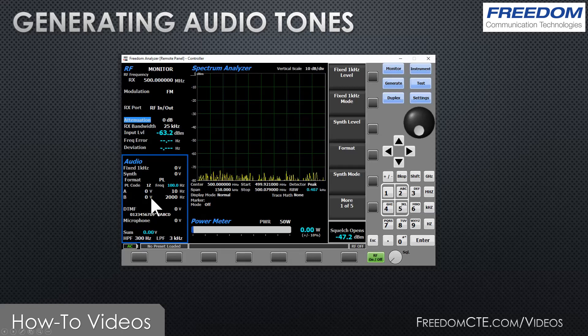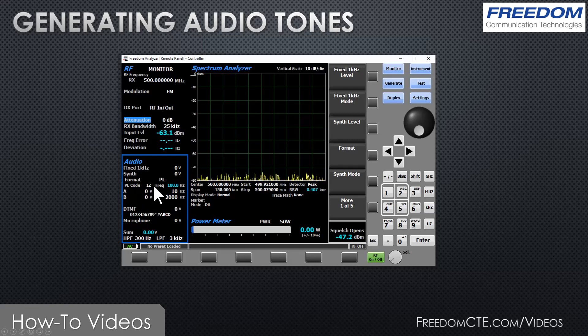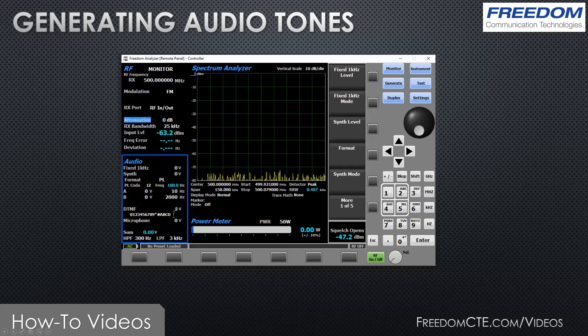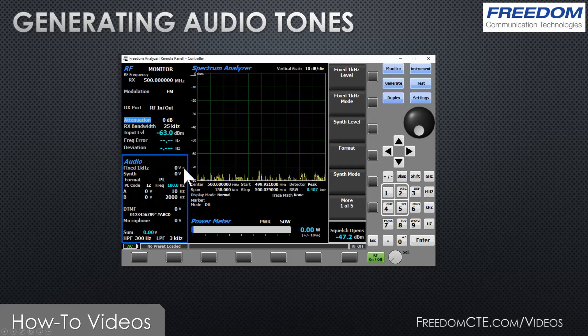The most important thing you should realize upfront is that there are basically two modes of operation. Right now I'm in monitor mode, as you can see up here. By pressing the blue monitor button I'm in monitor mode. In this mode I am NOT generating a carrier, therefore I'm not modulating a carrier with the audio. The audio zone can be thought of as an audio function generator. The audio that I configure here will be available at the mod out port on the front of the instrument, so all of my settings use the units of volts peak.